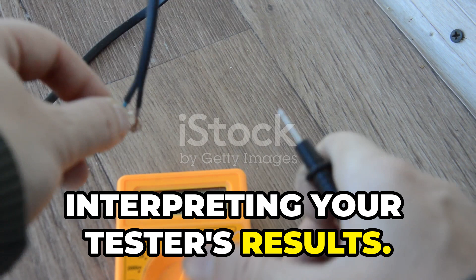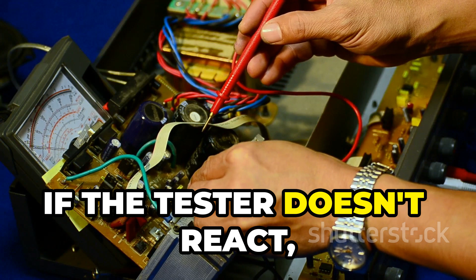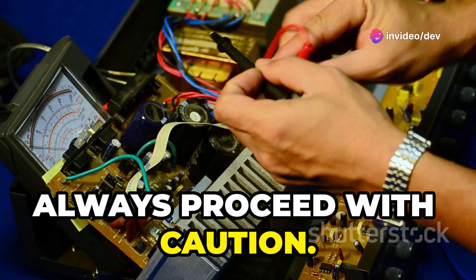Section 5. Reading the signs: interpreting your tester's results. Understanding what your tester is telling you is crucial. A light, beep, or vibration means there's live electricity. This means danger — do not touch the wires or outlet. If the tester doesn't react, it means there's likely no voltage. However, this is not a guarantee. Always proceed with caution; sometimes a weak signal might not be detected. Remember, it's better to be safe than sorry.